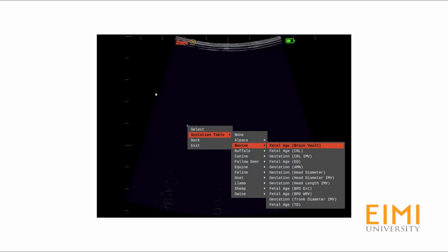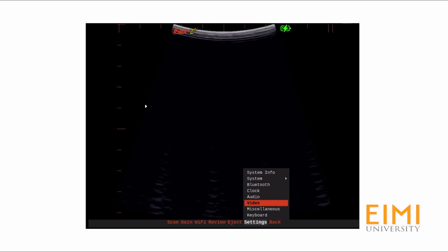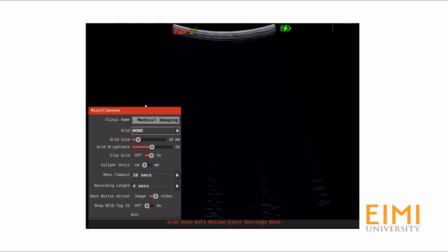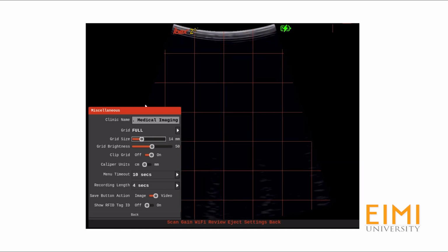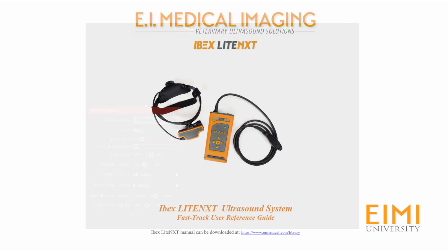Pressing the triangle key before starting a measurement brings up a menu that allows the selection of a gestation table for fetal aging. This table will persist for additional measurements until it is changed or removed. The studies from which this data was extracted are referenced at the end of the user manual for further information. To apply a grid overlay to the screen, navigate to the Settings menu and select Miscellaneous. Here you can change the grid from the default tick marks to a full grid display, adjust the size of the squares, and adjust the brightness of the overlay, among other preferences. Please see the Lite NXT user manual for more details and additional features.